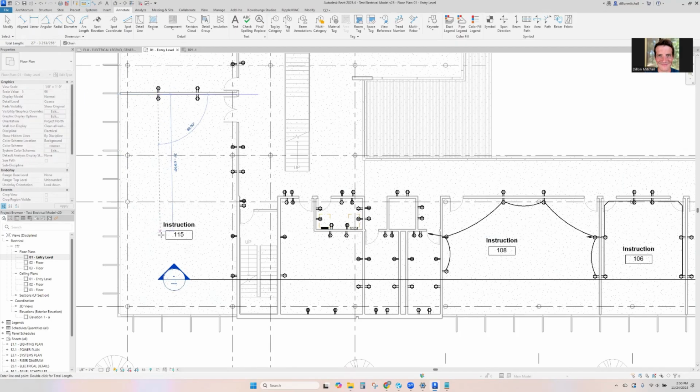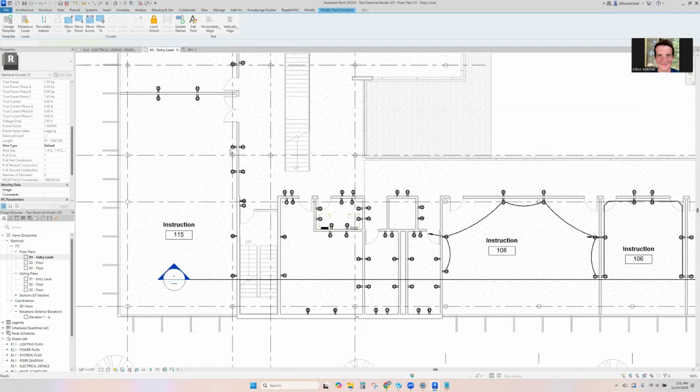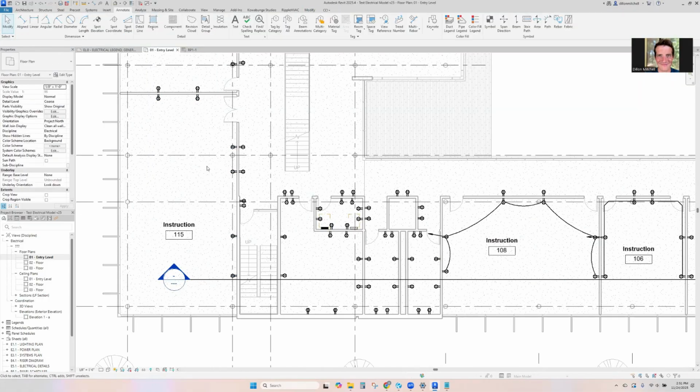So we go here, here, here. So 68 plus 10 up, 10 down, that gets us to 88. And then if we look at the length for this circuit, 81, that's pretty close, honestly, for what the total circuit length is going to be. Okay, that's pretty good.